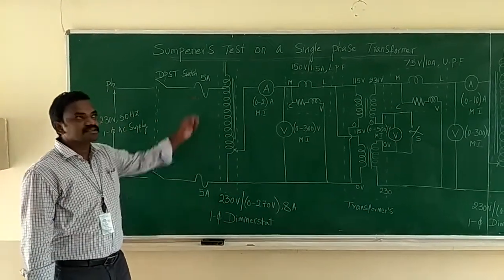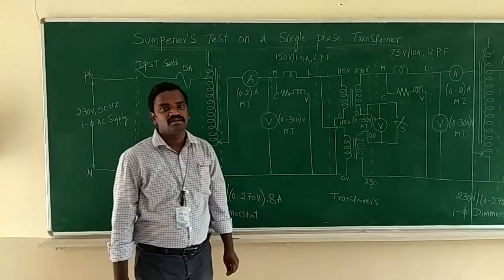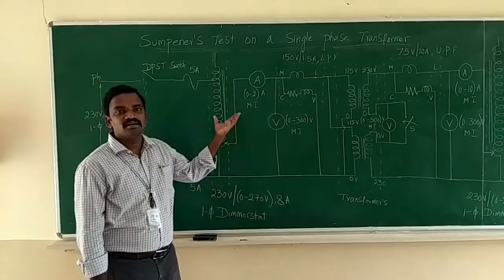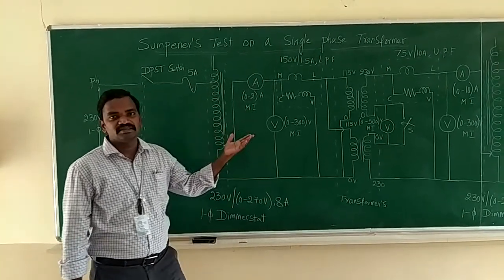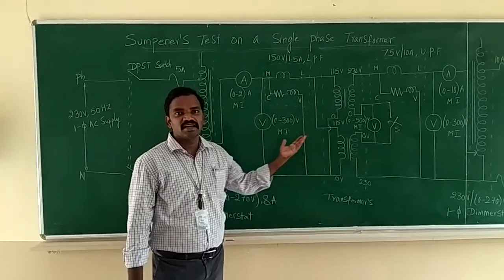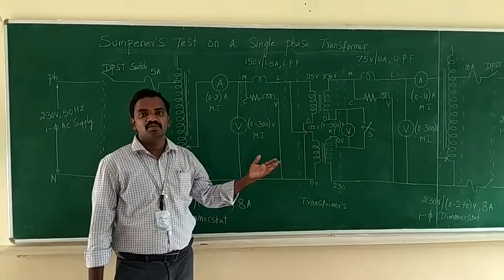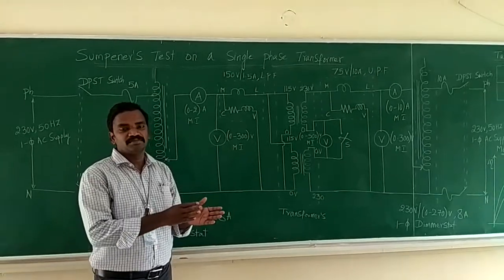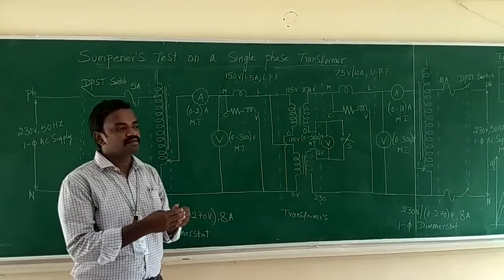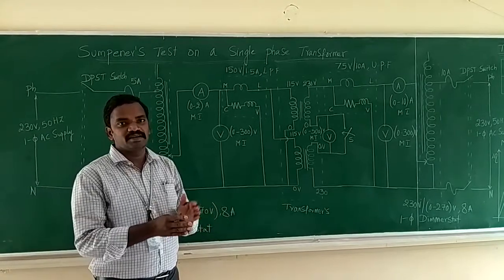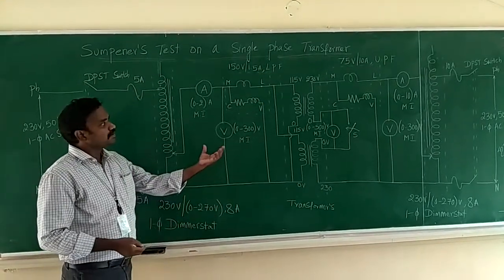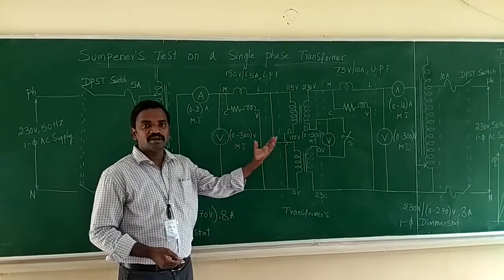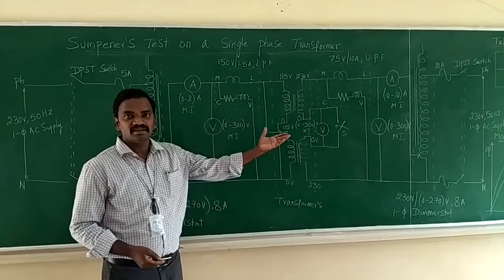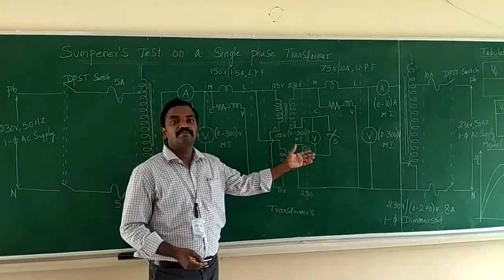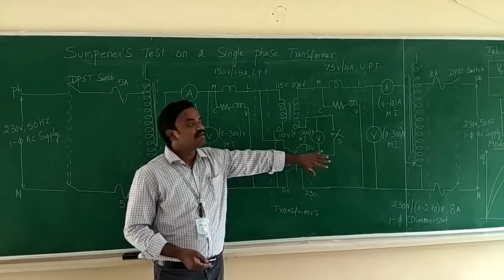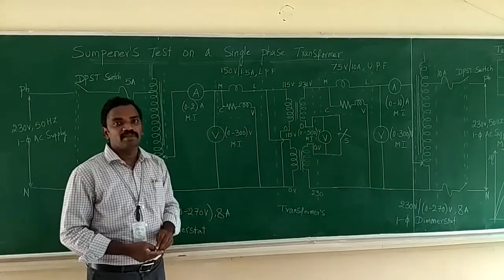I want to discuss Sumpner's test on a single phase transformer, where the test will determine the efficiency and the regulation of two identical transformers in one step. Whereas in the OC and SC tests, we determine the efficiency and the regulation by conducting separate tests. But here we do one experiment to determine the efficiency and regulation, and we can also determine the temperature rise of the transformers. This is also known as the back-to-back test.